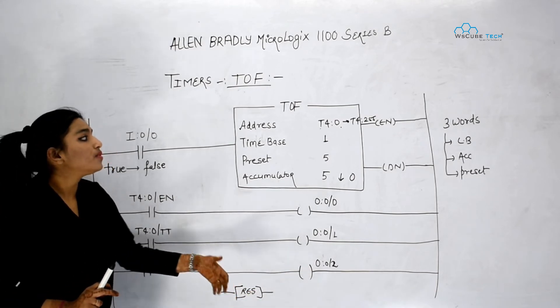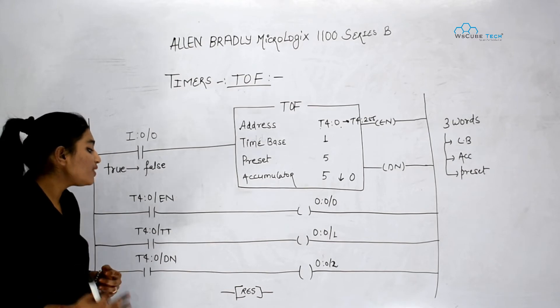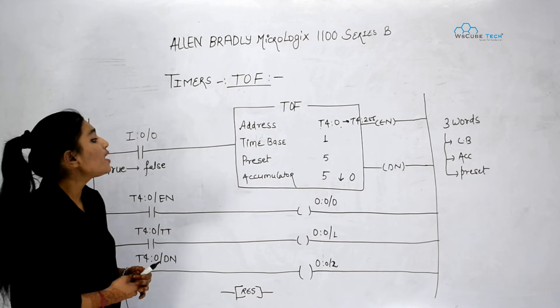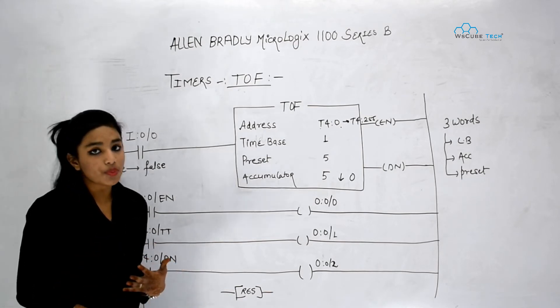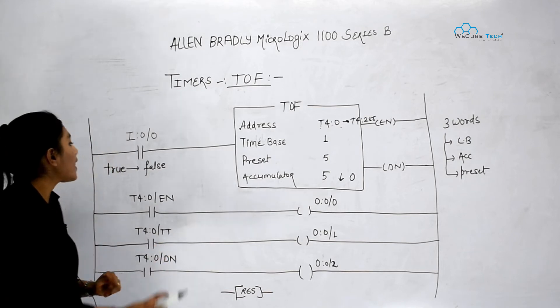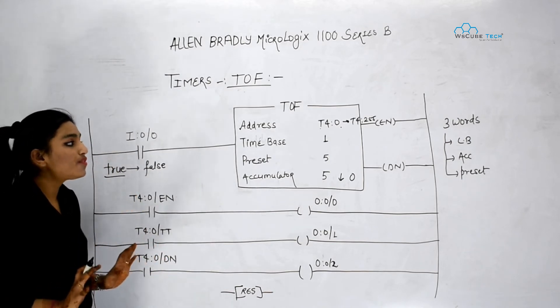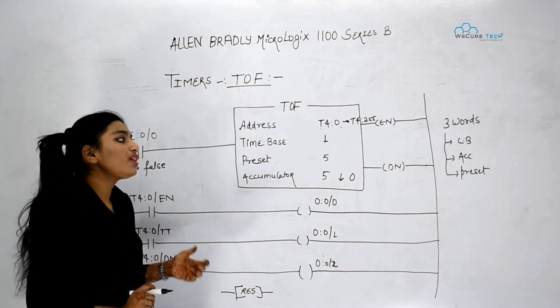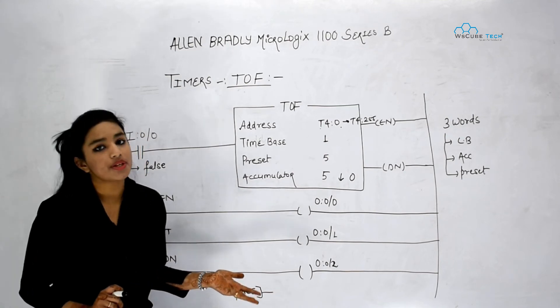So this is how working of TOF. Next one more thing that we can't use reset instruction to reset our TOF. It means when I want that our accumulator again becomes equal to preset, that time what I can do I can make my rung true. That's it. So we can't use reset in that. And one more thing that in PLC TOF takes 3 words memory. One is for control bit, one is for accumulator and one is for preset.